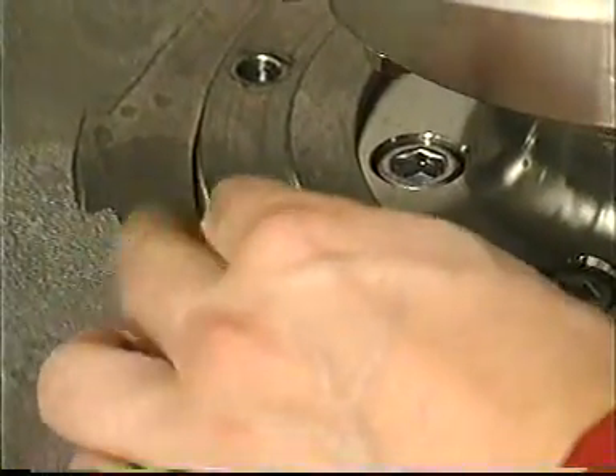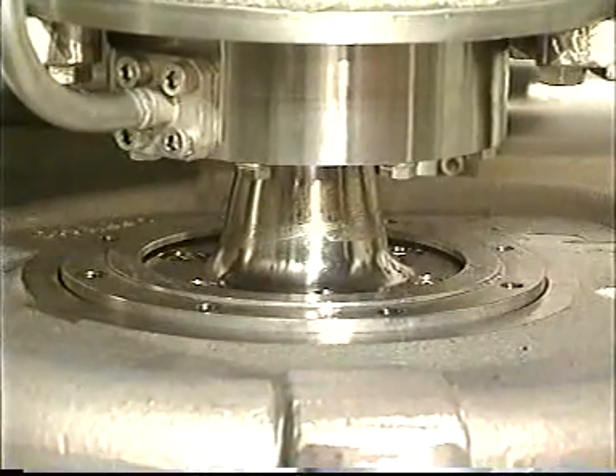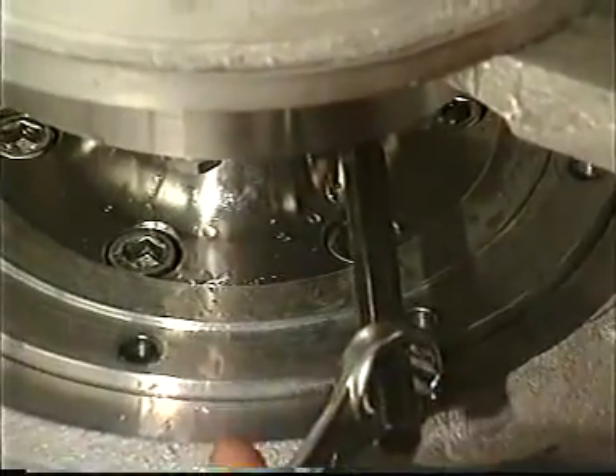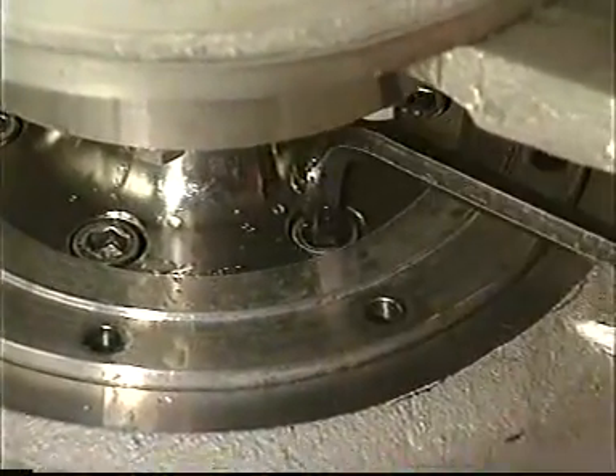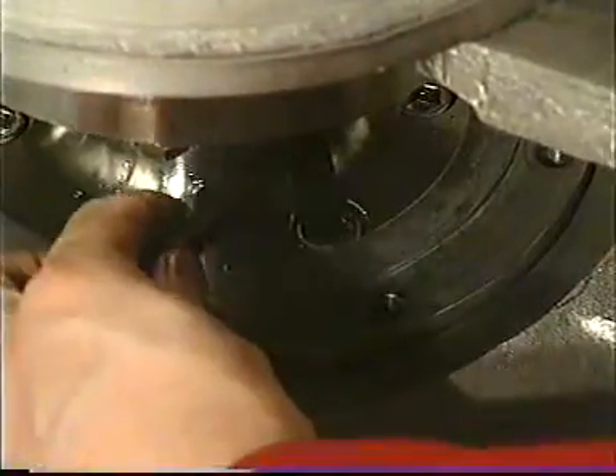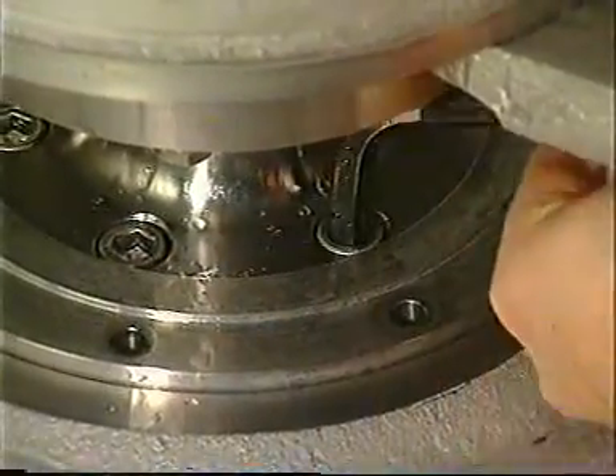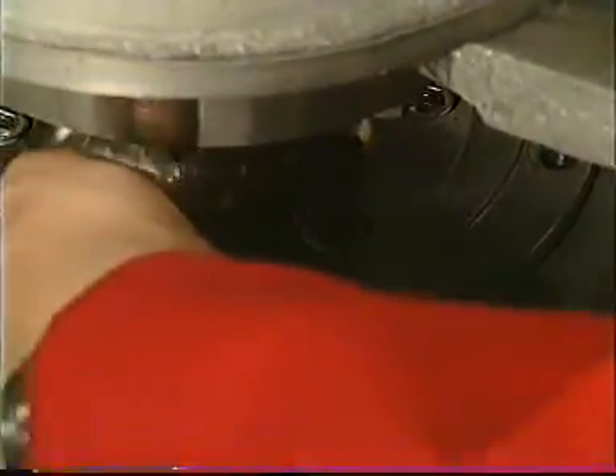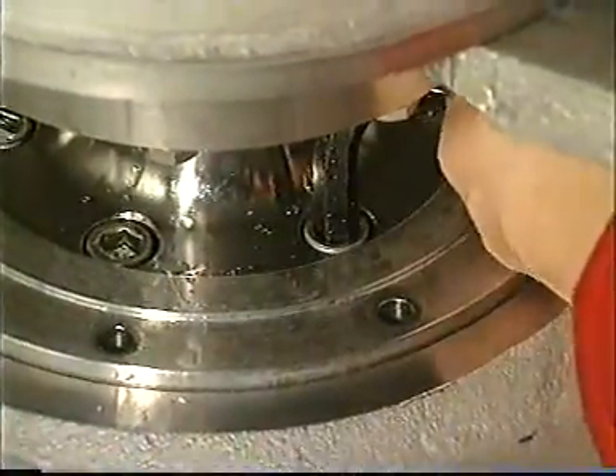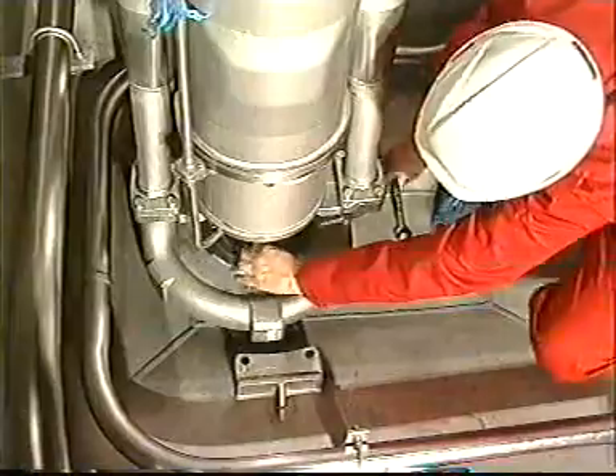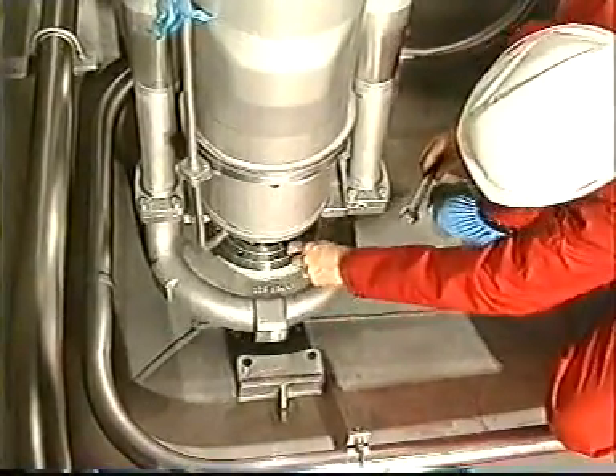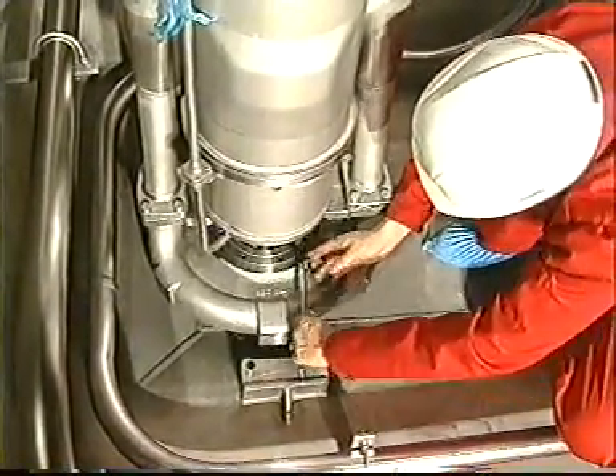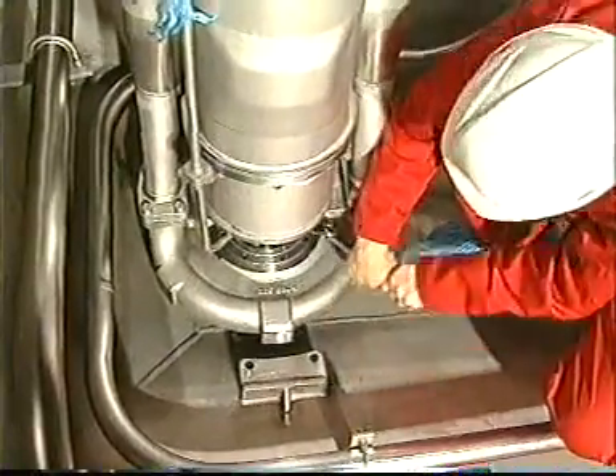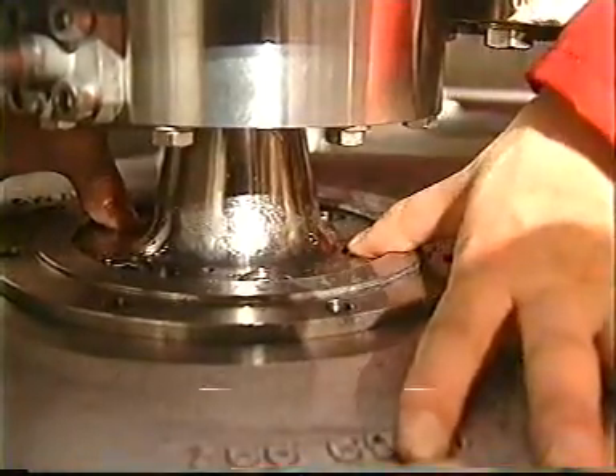Loosen the bolts for upper wear ring support. Then loosen the bolts for impeller hub, 2 turns only. Turn the impeller clockwise for easier access and better working condition for loosening the bolts. Press down the bolts and pump impeller. When the pump impeller is loose, remove the bolts.